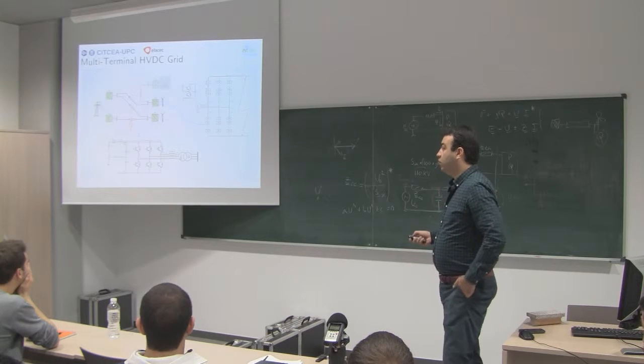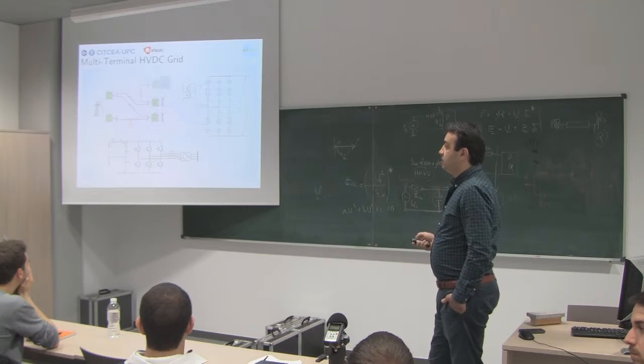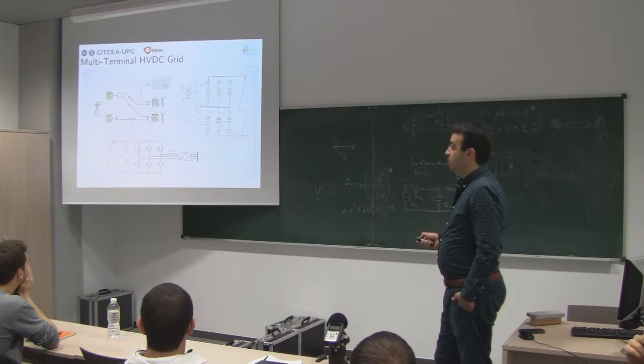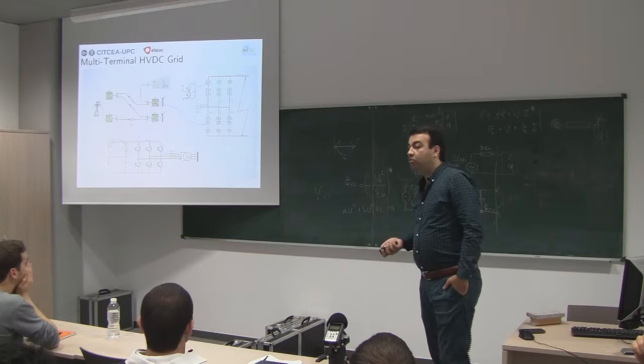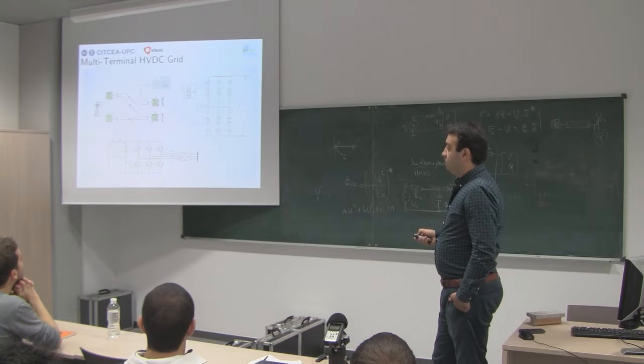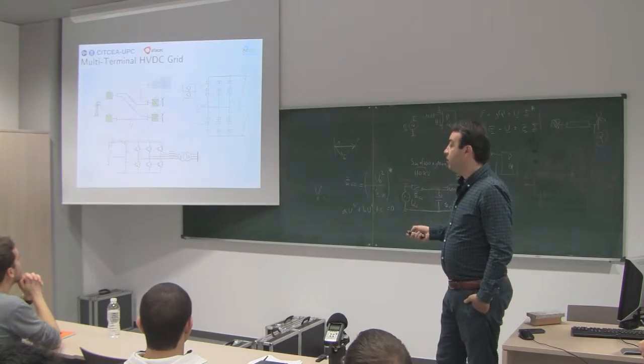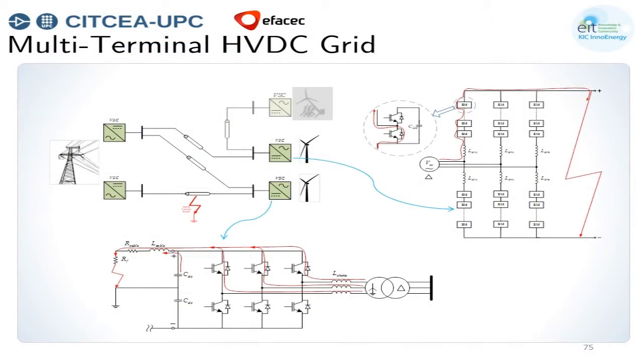This is the conventional two-level VSC topology. You know that you have 3 arms, 3 legs, and then mainly 6 sets of switches. But the problem is that when you have a short circuit fault here, depending on the grounding scheme of this transformer, it can even be a pole to ground, but mainly a pole to pole fault. Because of the presence of these anti-parallel diodes of the IGBTs, the current will permanently flow to the fault point, and you are not able to interrupt it. Even if you block the IGBTs, the current will flow. So it means that we don't have any control over the converters during the DC fault.